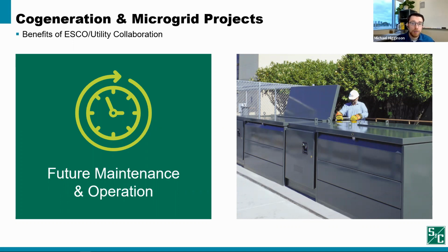In the case that they're responsible for maintaining this local equipment, it's best if the utility is engaged in the system design and the interconnection design. This collaborative process can help ensure the utility is happy with the design and able to operate the system going forward. To the extent practical, it's best to keep the microgrid equipment consistent with local utility equipment and practices to ensure it will work well for utility personnel.